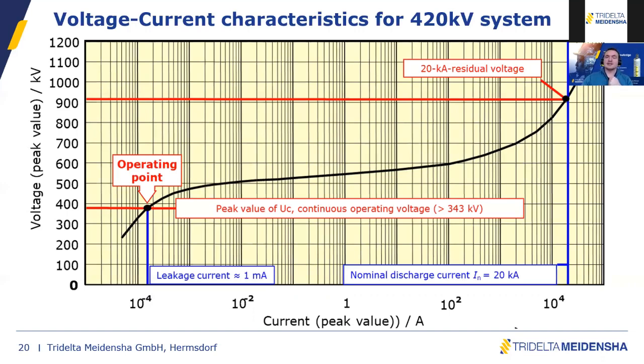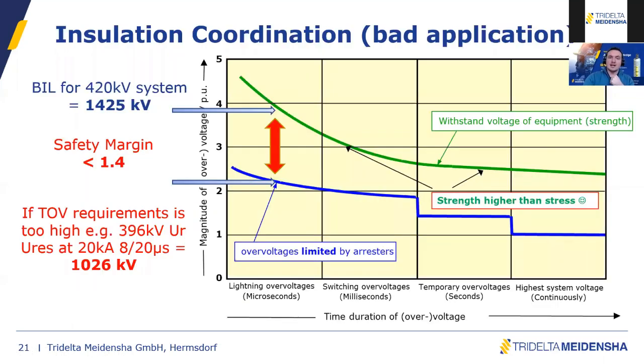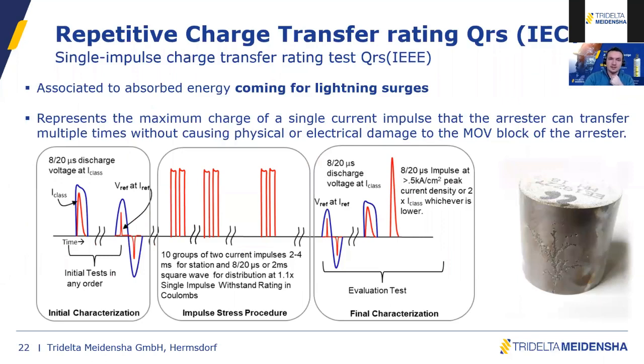But you have to make sure that the energy coming from lightning or switching will not exceed the MOV properties. And this is why two important energy ratings now come. One is called repetitive charge transfer, with a Qrs rating. This is a new introduction from the IEC 60099-4 from 2014. It is a rating which is mainly associated with lightning surges. Basically, the idea here is to have a statistical approach to look at the mechanical integrity of the blocks after lightning surge injection.